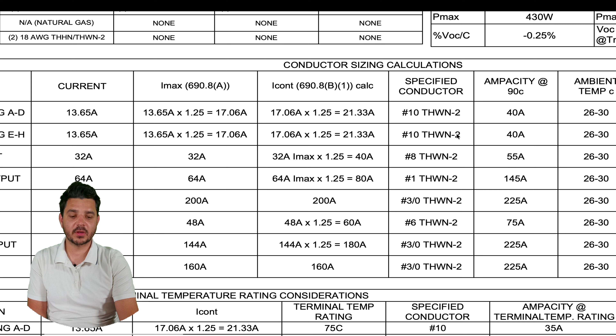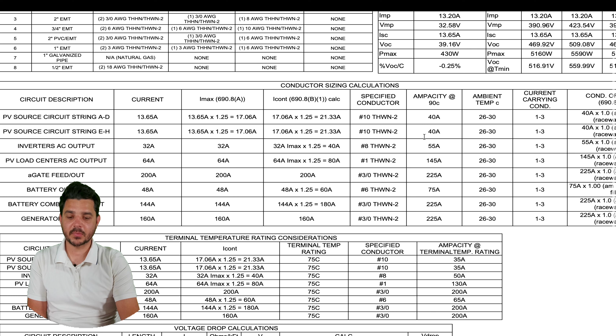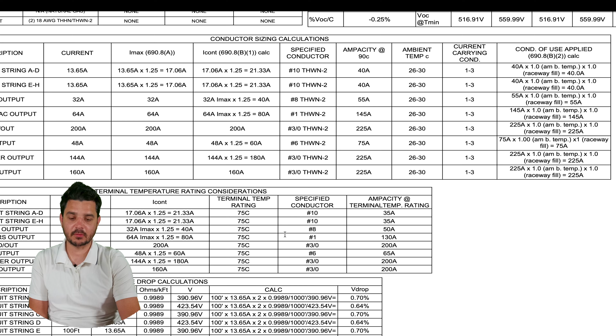Most of it's number 10s for the array. The inverter gets bumped up for that because it's 40 amps. Number 8s. It doesn't look like we need to go to number 6s for the distance. Let me check. No, with the distance, we're still fine with number 8s.